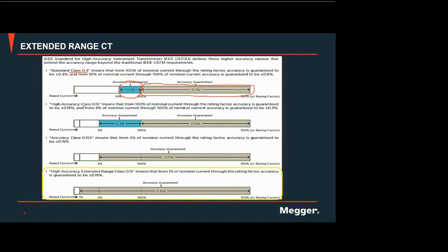Looking at the 0.15 class here, same thing. If you have 100% rated current, then you can have 0.15% error. And from 5% to 99%, maybe 99.99% current rating, then you can only have 0.3%. And looking at the 0.15S, which is more accurate than 0.15, here the S can have a 0.15% accuracy down to 5% of the rated current.